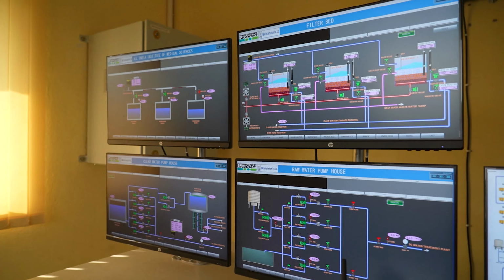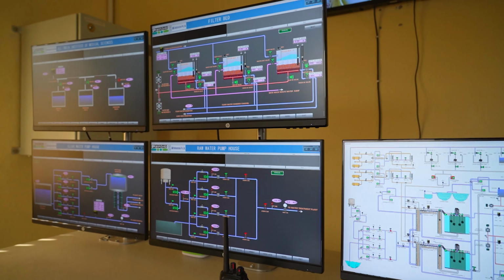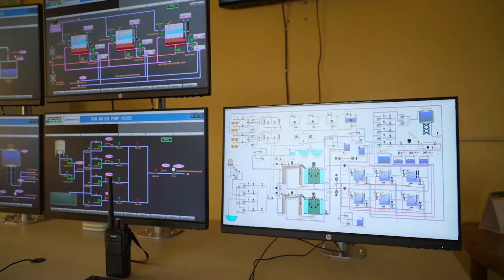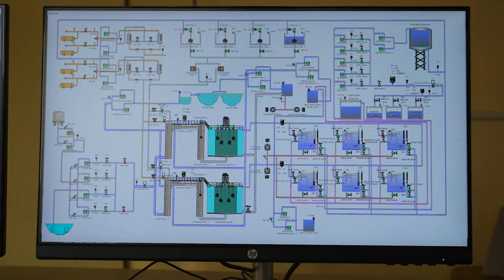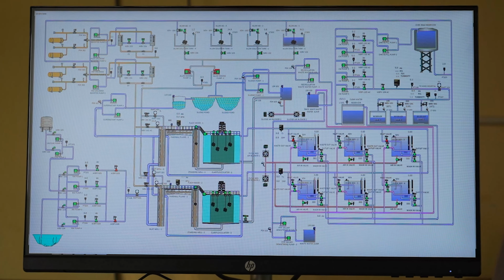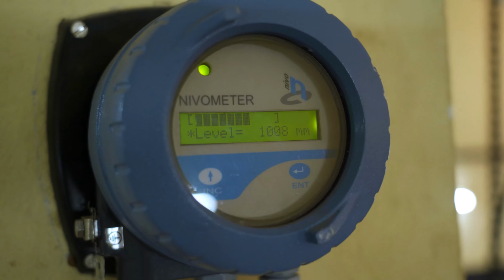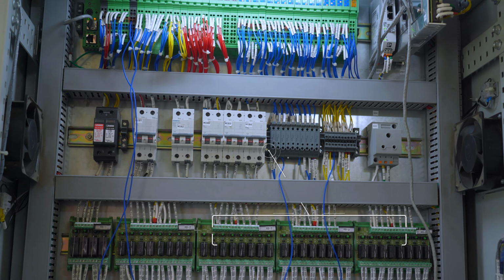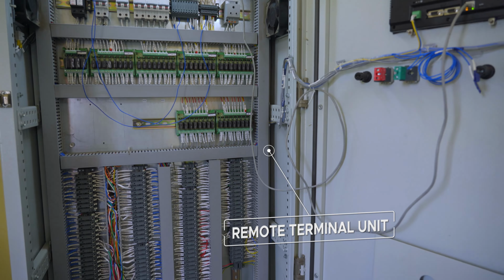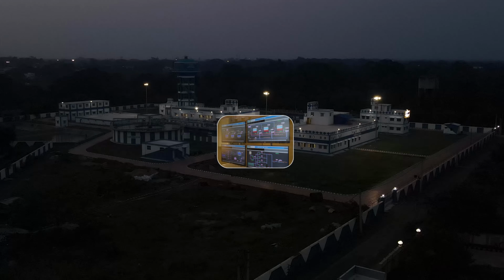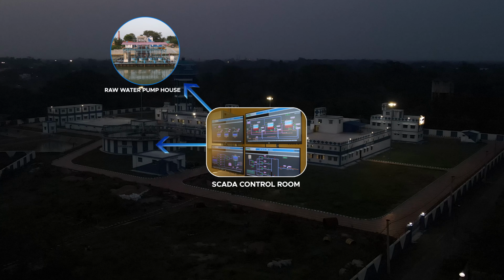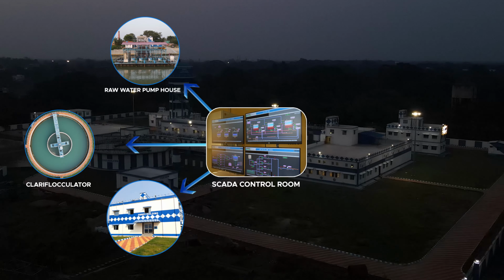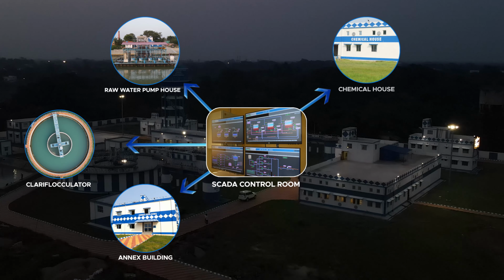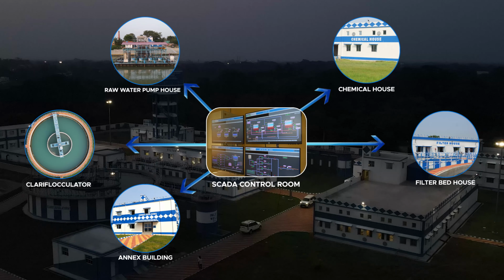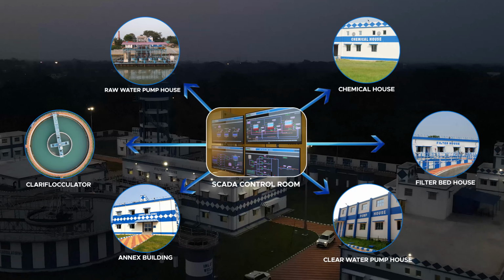Multiple remote units at different sites transmit the data collected to a single master station which displays the information in a browser. Sensors and control relays are attached to remote terminal units (RTU). These remote units are the raw water pump house, clariflocculator, annex building, chemical house, filter bed house, and clear water pump house.